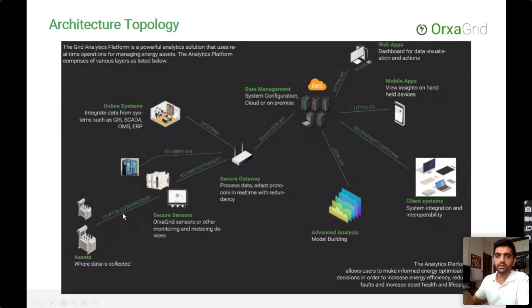Then after that, if you have any other analog inputs, like temperature input, pressure gauge inputs, or any other sensor inputs which are 4 to 20 milliampere standard sensors. So those go in your analog inputs, and then you have digital input output for statuses and remote controlling. These inputs are traditionally connected to a substation RTU or a gateway unit, and then over an industry standard protocol such as IEC 104, the data is then pushed to your data management layer. So that is your traditional way of doing it.